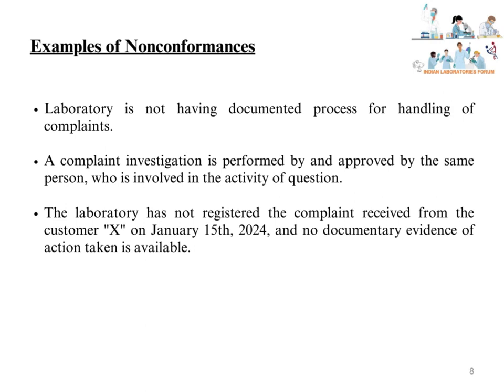Examples of non-conformances as per Clause 7.9: First, the laboratory is not having a documented process for handling of complaints. Second, a complaint investigation is performed by and approved by the same person who is involved in the activity in question. Third, the laboratory has not registered the complaint received from customer X on January 15, 2024, and no documentary evidence of action taken is available.